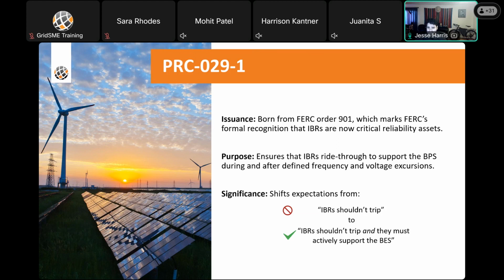The purpose of this was to ensure that IBRs ride through to support the BPS during and after defined frequency and voltage excursions. Why this is so significant is right now, currently under the PRC 24-3 standard, the expectation is that IBRs just shouldn't trip. And this is going to shift that expectation to not only should they not trip, but they have to actively support the BES.